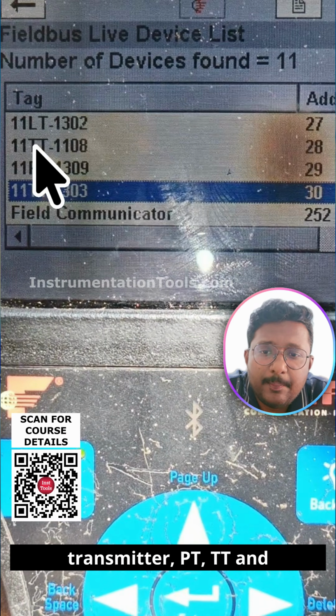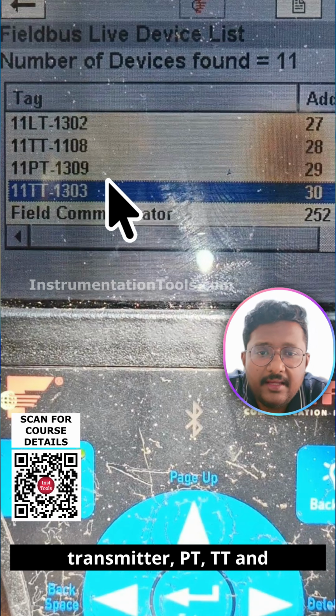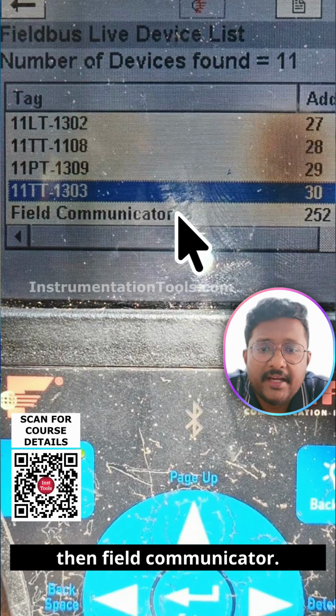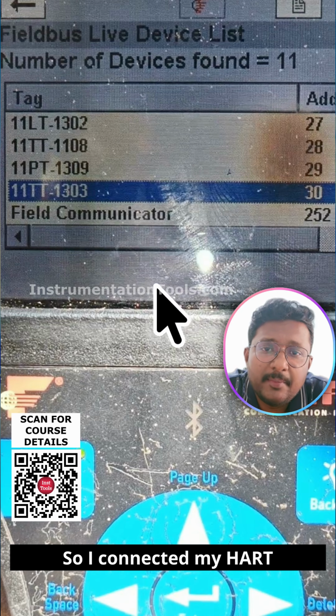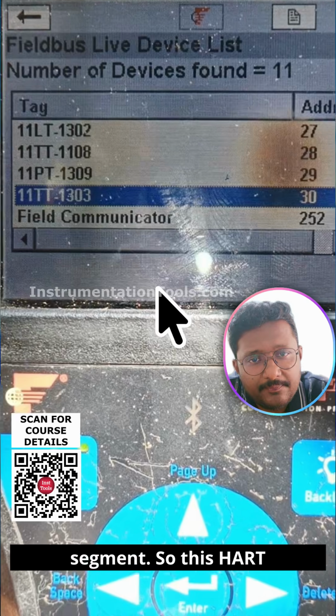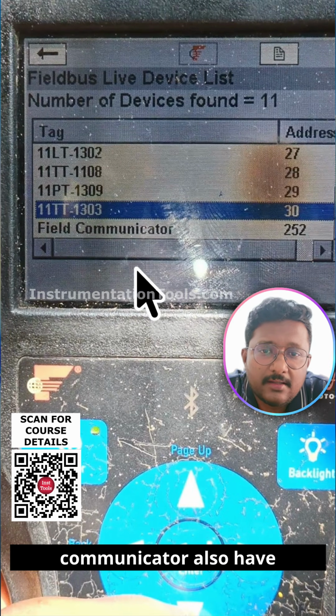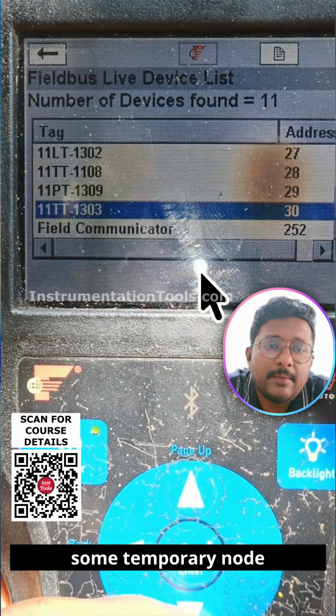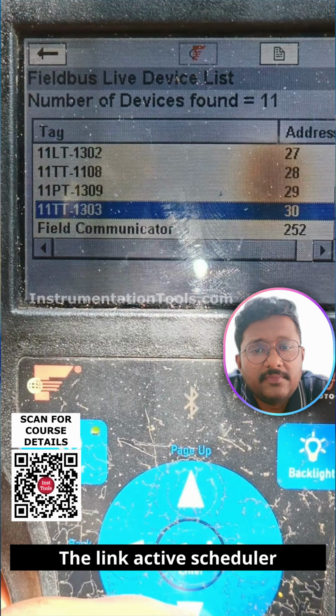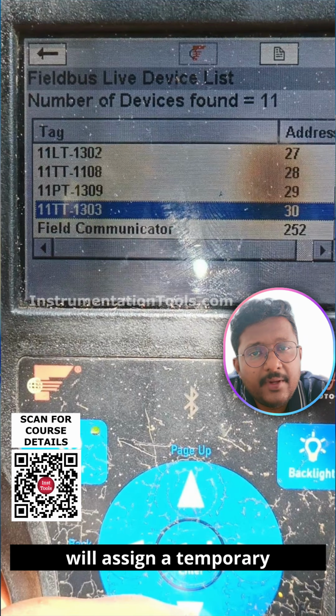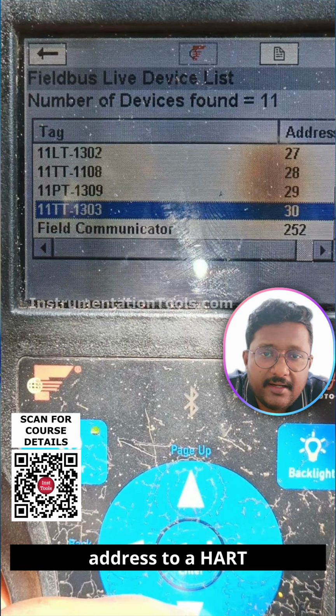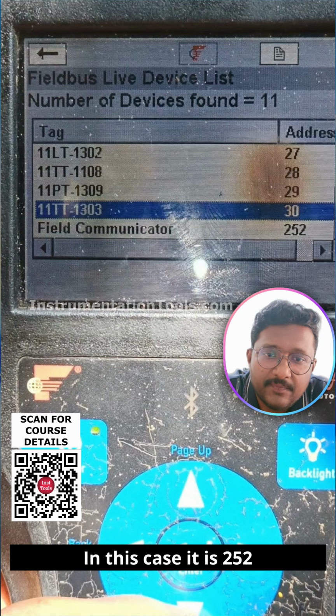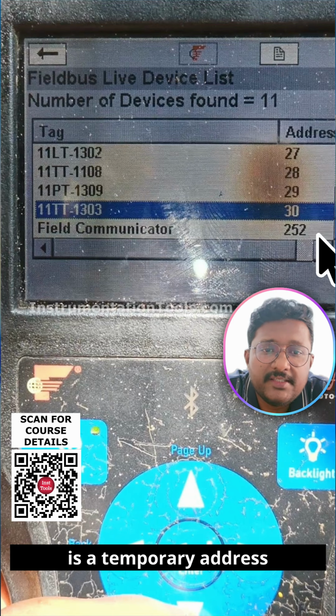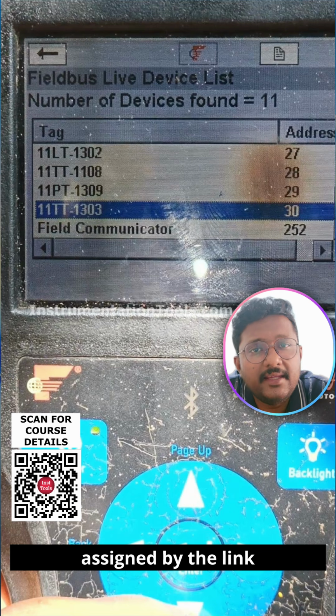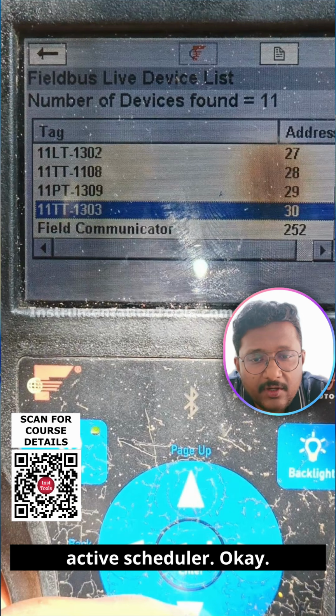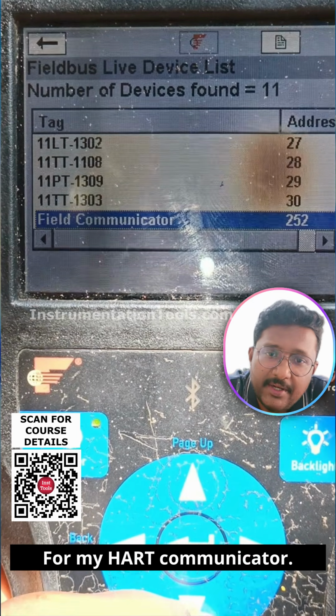So I connected my HART Communicator to the segment. So this HART Communicator also has a temporary node address. The link active scheduler will assign a temporary node address to a HART Communicator. In this case, 252 is a temporary address assigned by the link active scheduler for my HART Communicator.